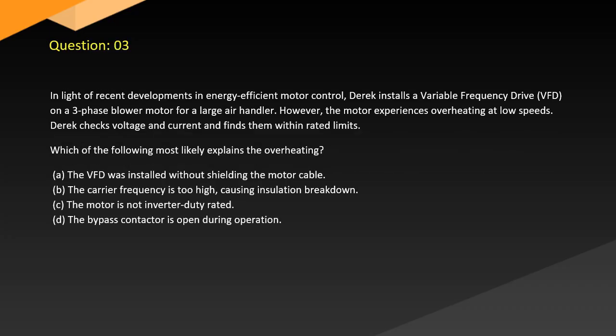Question 3. In light of recent developments in energy-efficient motor control, Derek installs a variable frequency drive (VFD) on a three-phase blower motor for a large air handler. However, the motor experiences overheating at low speeds. Derek checks voltage and current and finds them within rated limits. Which of the following most likely explains the overheating? A. The VFD was installed without shielding the motor cable. B. The carrier frequency is too high, causing insulation breakdown. C. The motor is not inverter duty rated. D. The bypass contactor is open during operation.